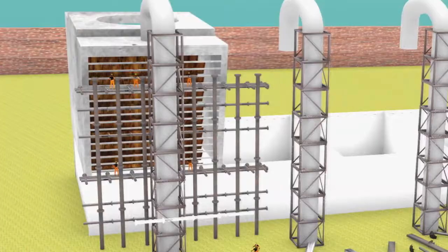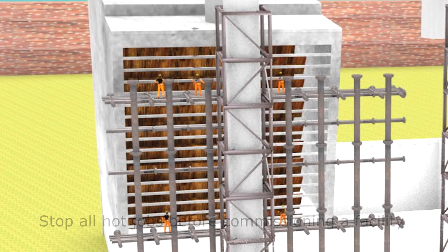At the time of opening the tie-in connection, the header and riser pipes were undergoing repairs. Investigation revealed that at the time of the incident, a total of 16 hot jobs were going on. The process of stopping all hot work before commissioning of any new system or facility was not adhered to.